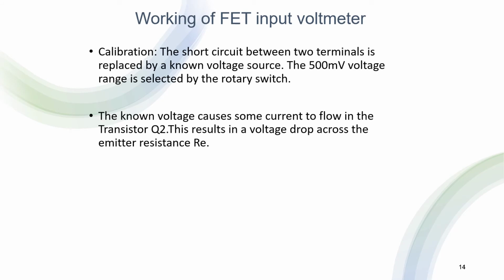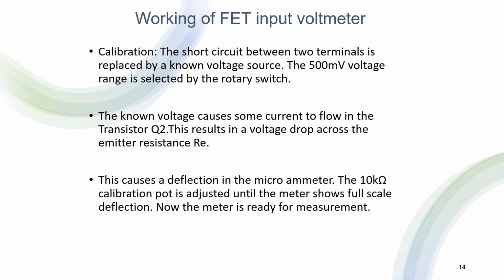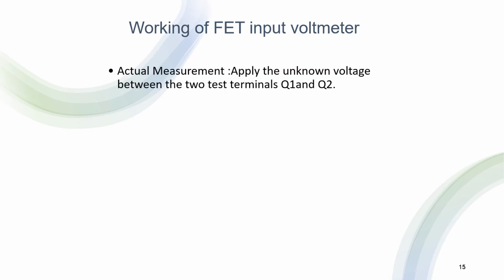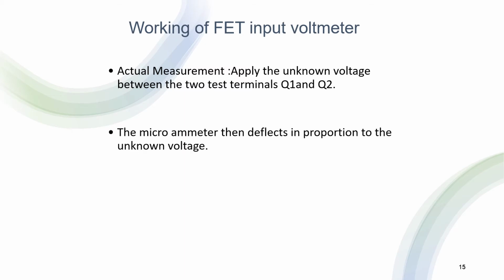Next is the calibration section. Now the short circuit between the two terminals is removed and a small voltage of 500 millivolts is connected across the test terminals T1 and T2. The 500 millivolts voltage range is selected by means of the rotary switch, that is the range switch. Now, the known voltage source causes current to flow in the drain of the FET. This causes an emitter current to flow in the transistor. This results in a voltage drop across the emitter resistance RE. This causes a deflection in the microammeter. The 10K calibration potentiometer is adjusted until the meter shows the full scale deflection, that is the 500 millivolts. Now the meter is ready for the actual measurement.